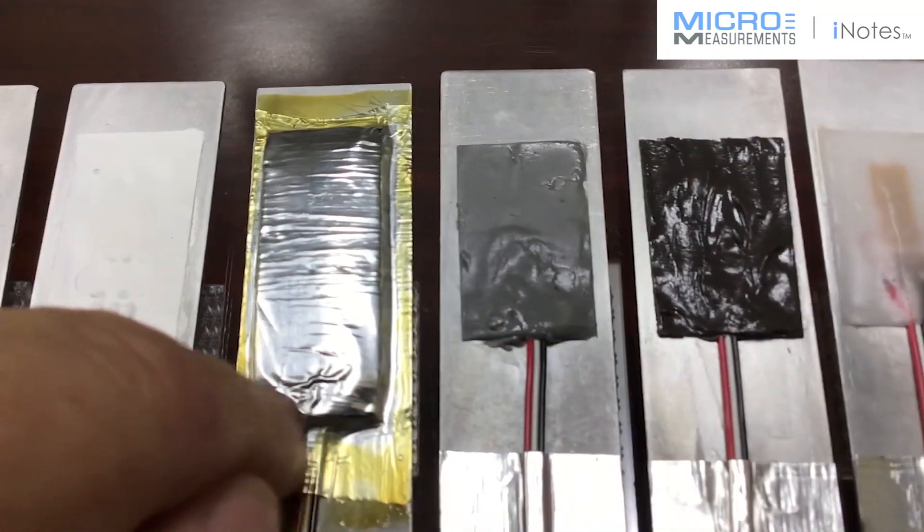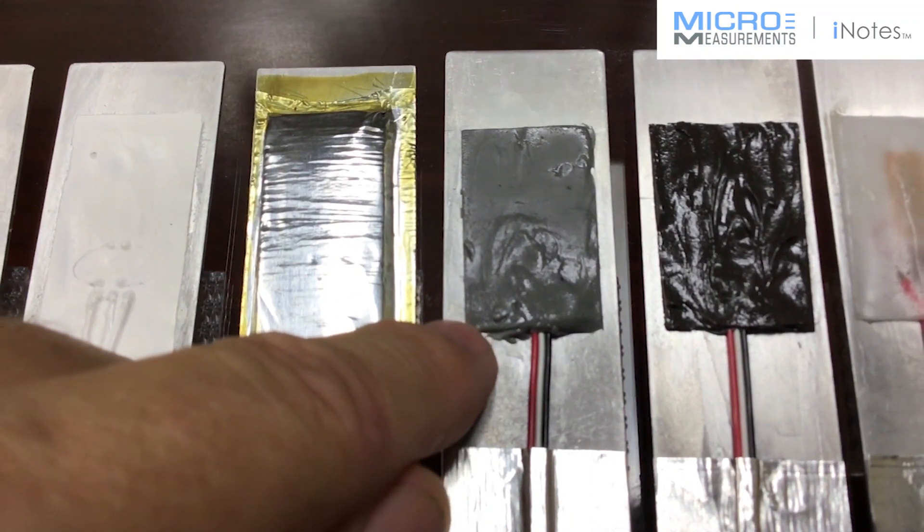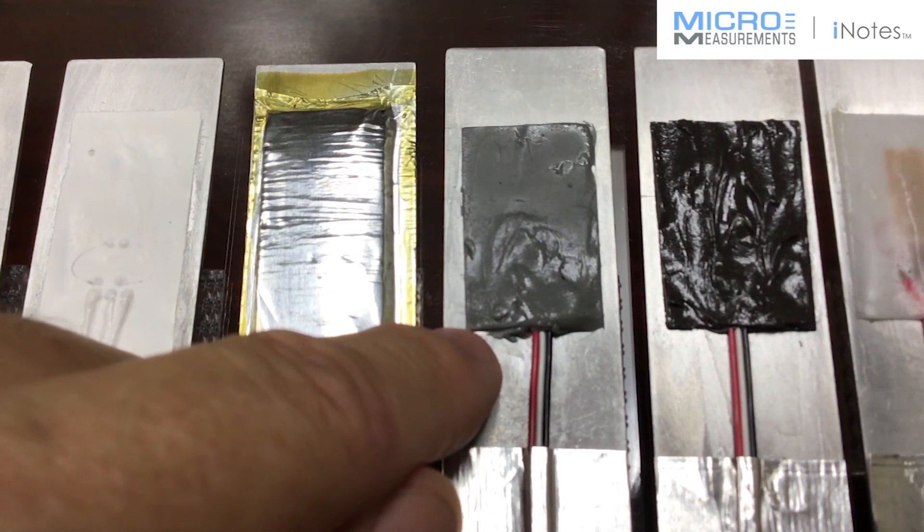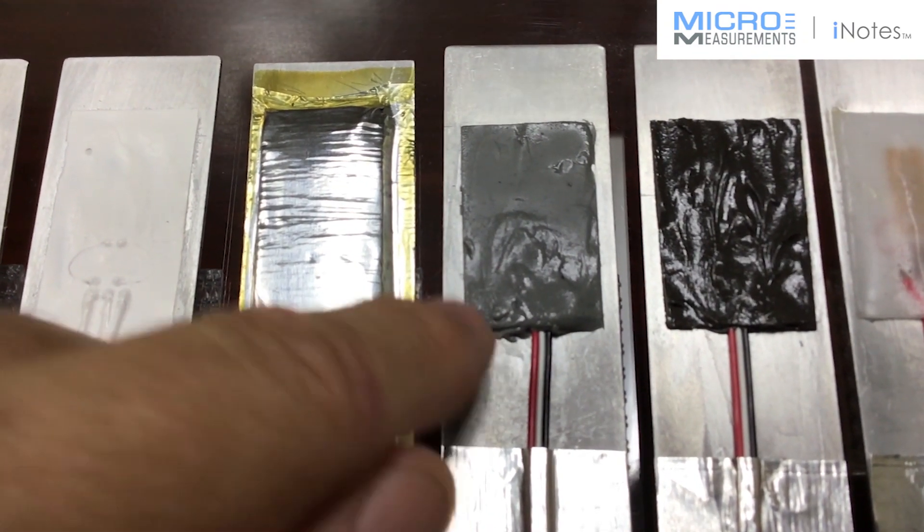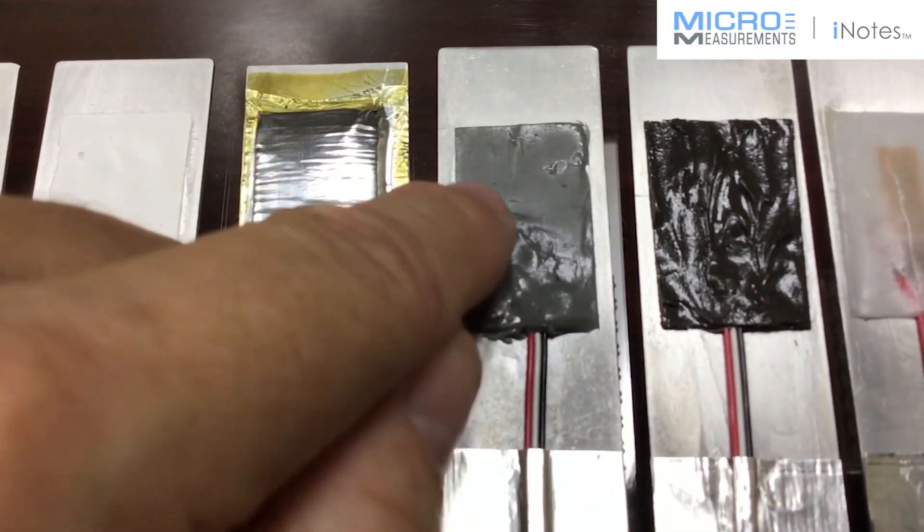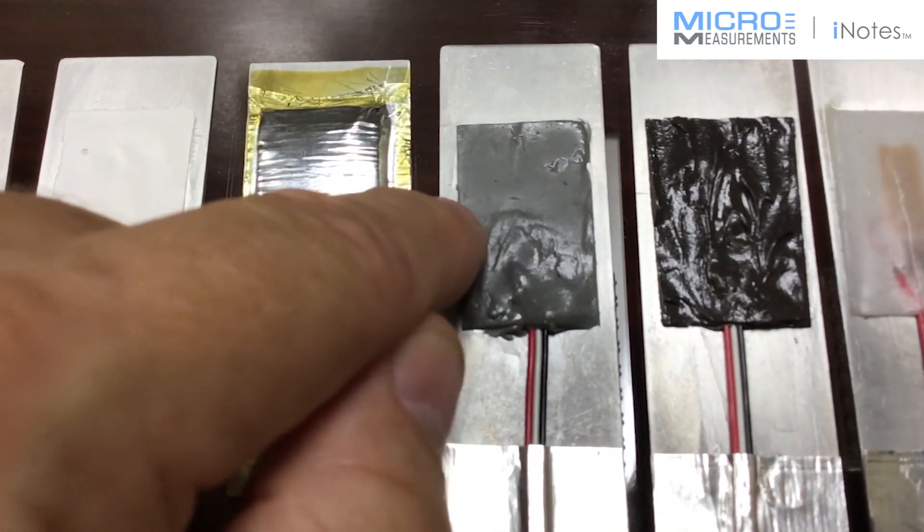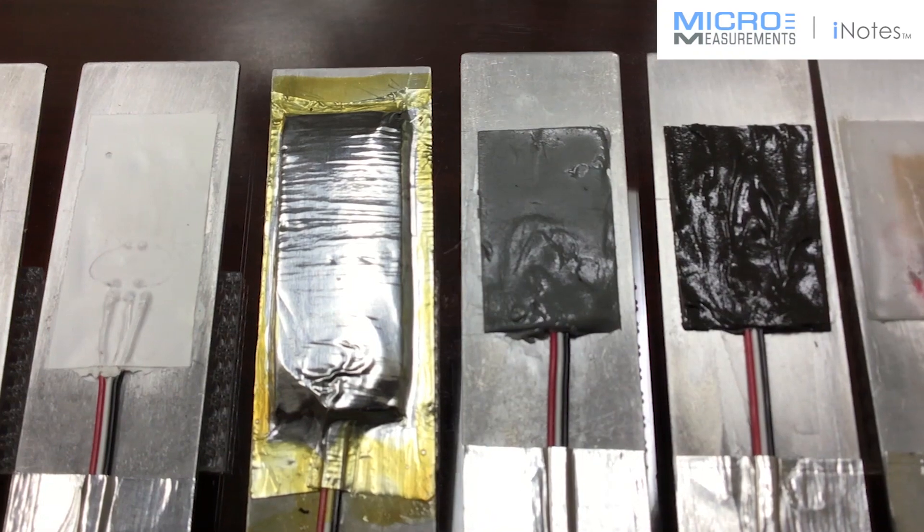The next one, this is M-Coat FBT. This is a butyl rubber. We take the butyl rubber and we throw some solvent in it and we shake it up so that we can put it in a big tube like a big tube of toothpaste. Then you can squeeze it out. I don't know if you can see this from the camera, but this coating is still tacky. It stays soft. It's a very good moisture barrier and also very low modulus.